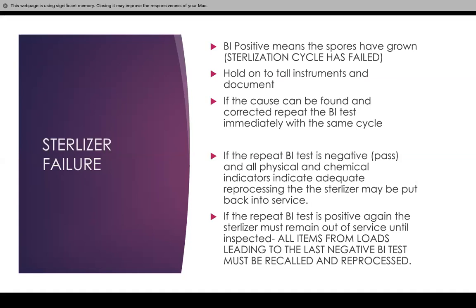If the cause can be found in the sterilizer, we do have technicians on hand — just notify the front desk or office managers and a person comes in right away to check everything. If the cause can be found, you can repeat one BI test immediately with the same type of cycle. If it's an unwrapped cycle, you have to place an unwrapped BI; if it's a wrapped cycle, use the same cycle. If there are no spores growing, you can go ahead and reuse the sterilizer, but you have to document everything.